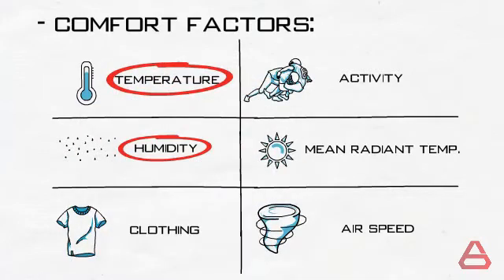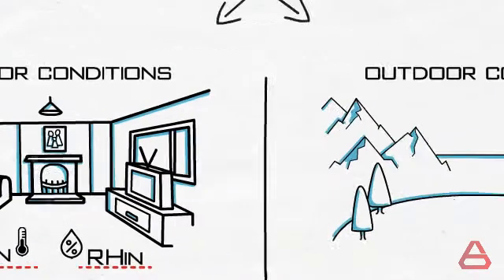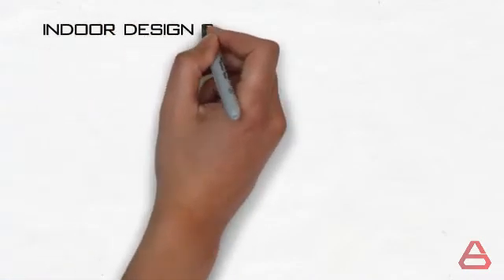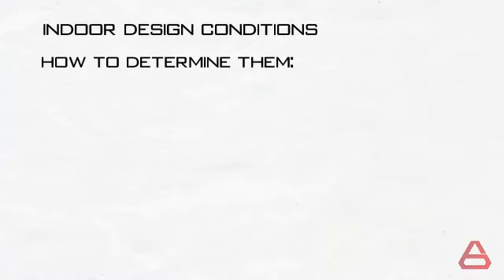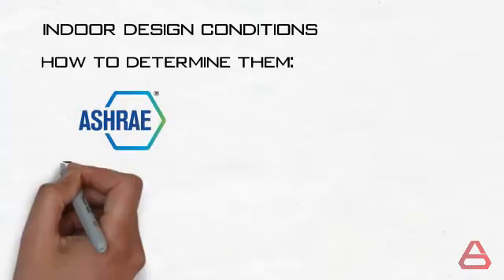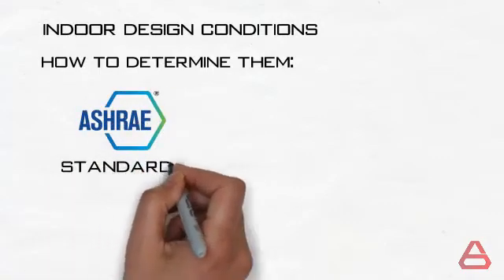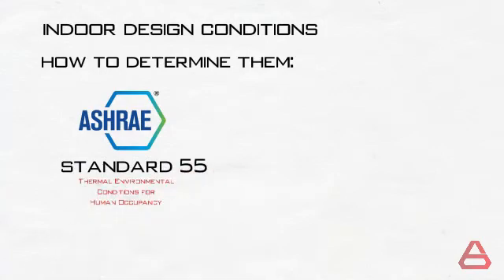Therefore, most of the time when indoor design conditions are mentioned, people refer to indoor temperature, T-in, and indoor humidity, RH% in. The conditions can be determined based on a certain standard from ASHRAE, named ASHRAE Standard 55, titled Thermal Environmental Conditions for Human Occupancy.